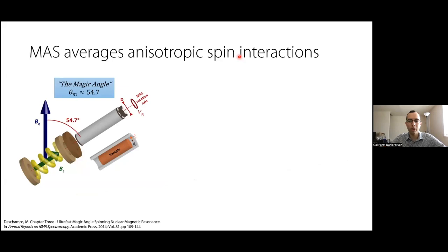However, these anisotropic spin interactions can be averaged by spinning the solid sample very fast in the rotor at an angle of 54.7 degrees with respect to the external magnetic field. That angle is called the magic angle, and therefore the method is called magic angle spinning NMR.